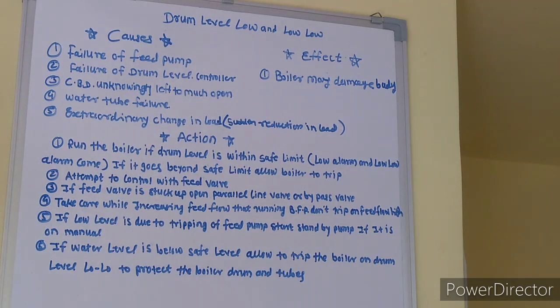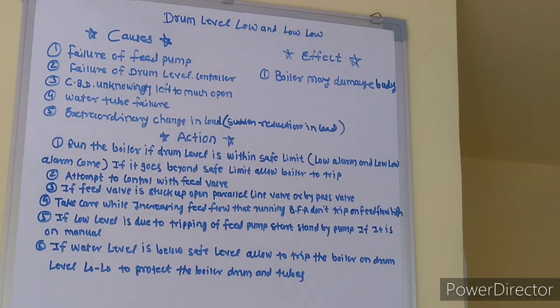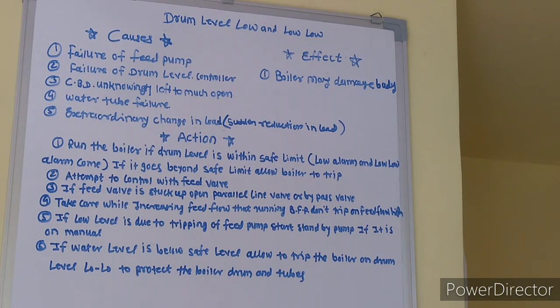Failure of feed pump. Failure of drum level controller. CBD unknowingly left open. Water tube failure. Extraordinary change in load — sudden reduction in load.